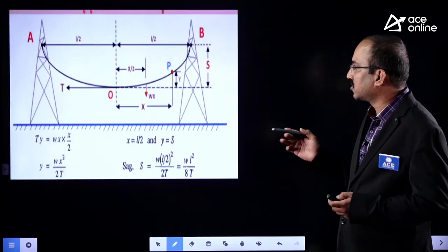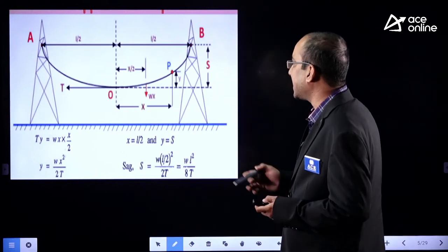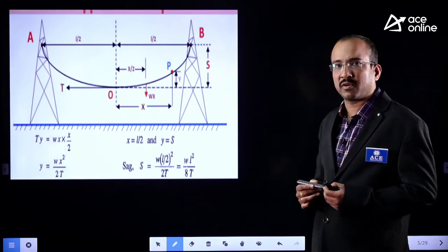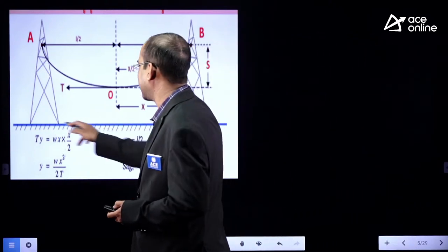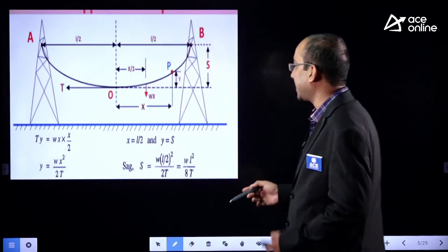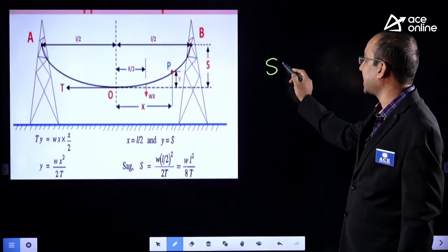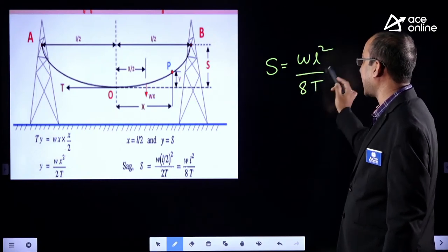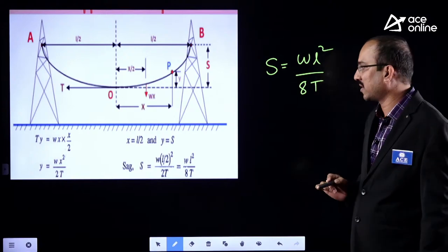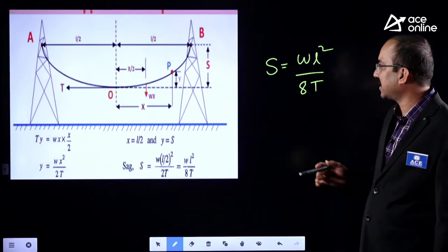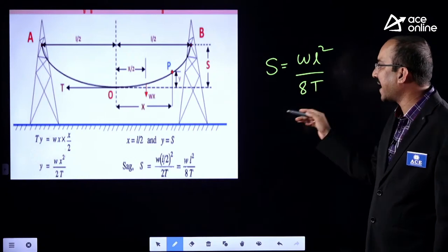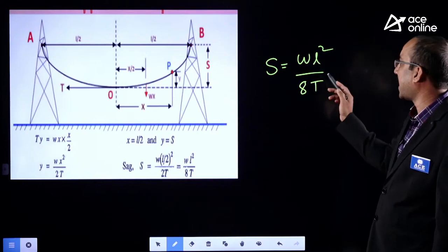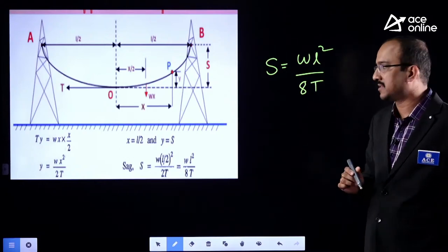How do you calculate the SAG? When the conductors are at the same support level, SAG S is equal to WL² by 8T. W is the weight of the conductor, L is the span length, and T is the tension.